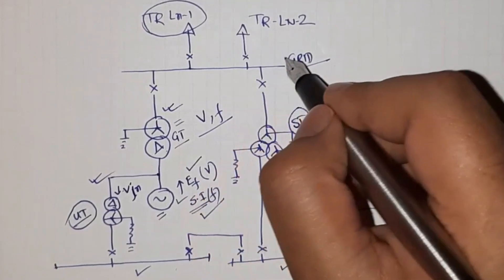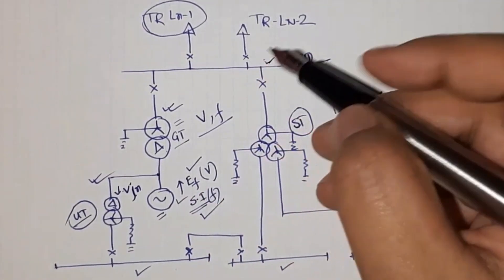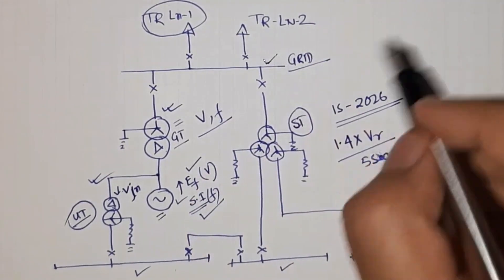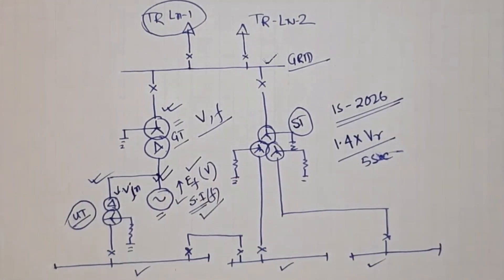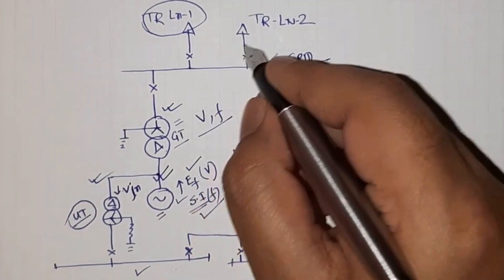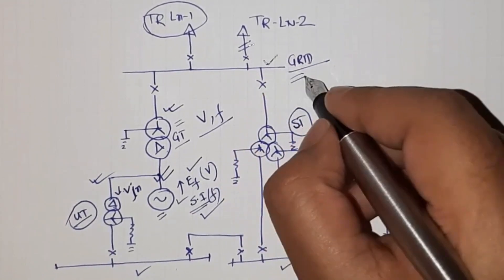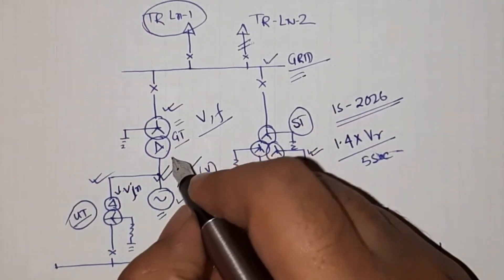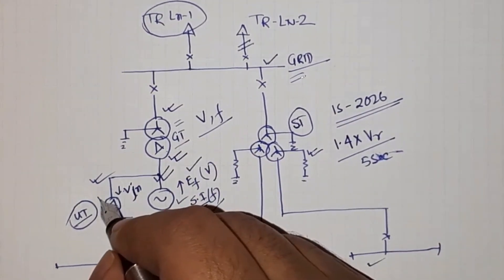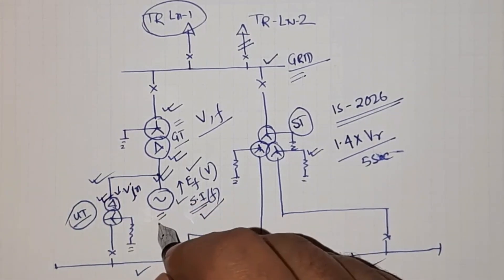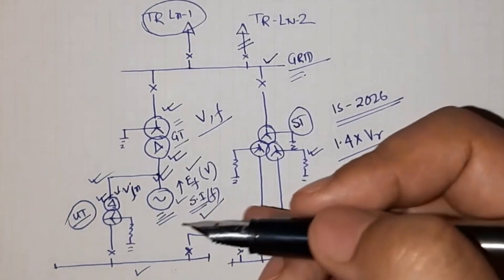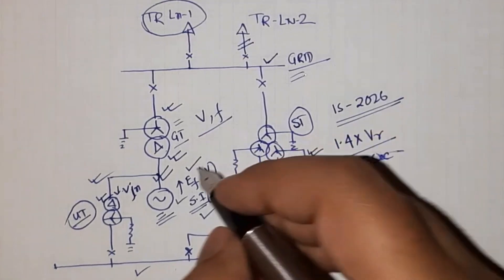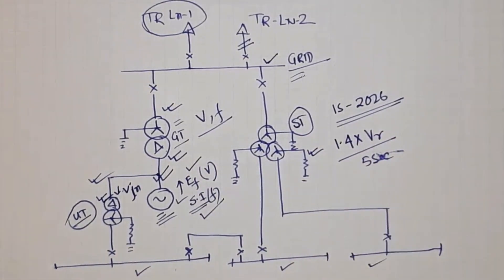The grid voltage is maintained at the same level — it cannot change. When there is a fault on the transmission line, the grid voltage will remain the same, so the station transformer voltage will remain the same and there will be no harm to the station transformer. However, the primary winding of the generator transformer and the unit transformer will face higher values of voltage and frequency, causing over-voltage and over-fluxing to these transformers. That is why they must have the over-voltage withstand characteristic.